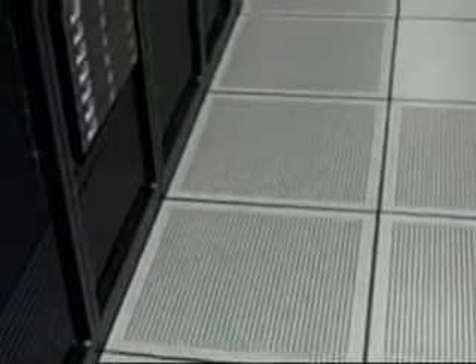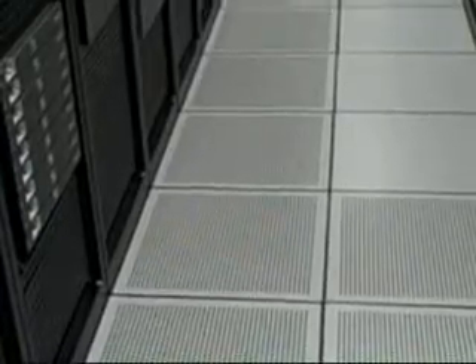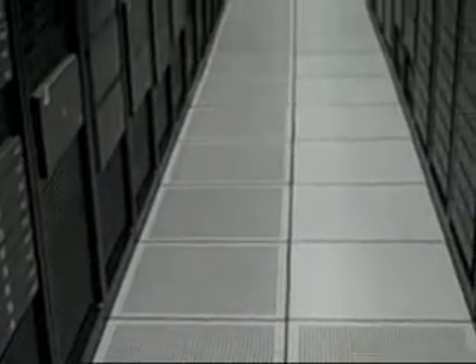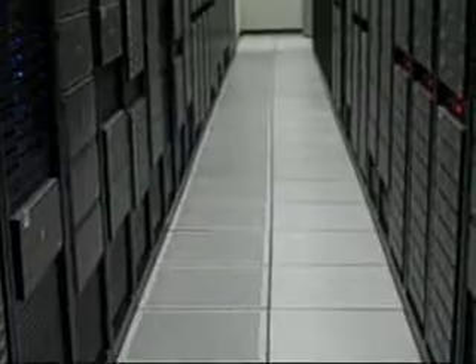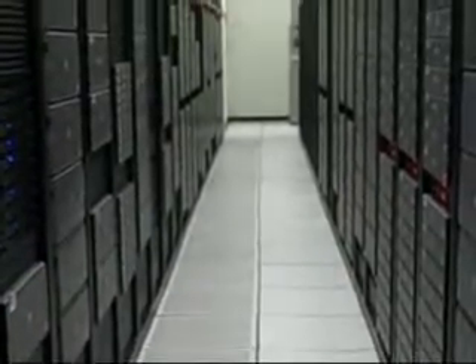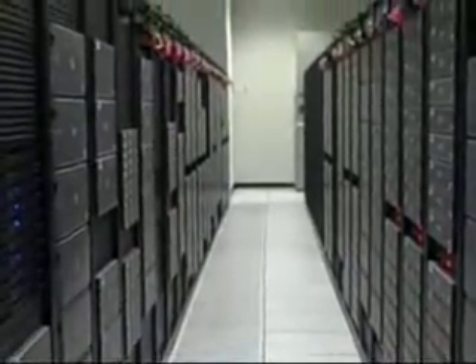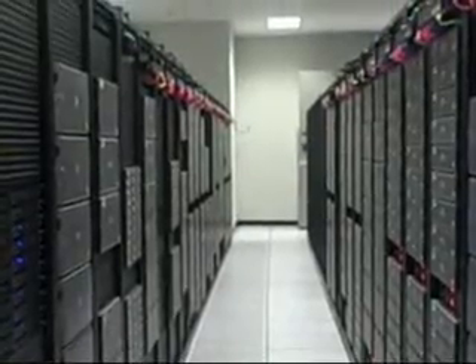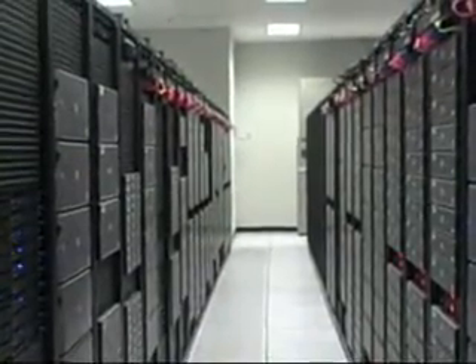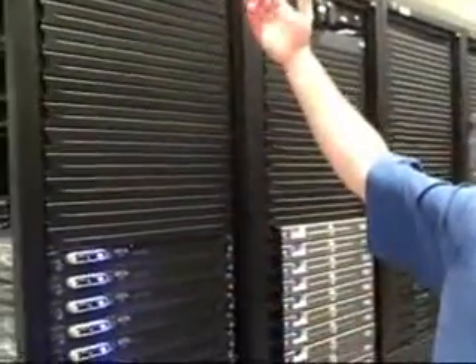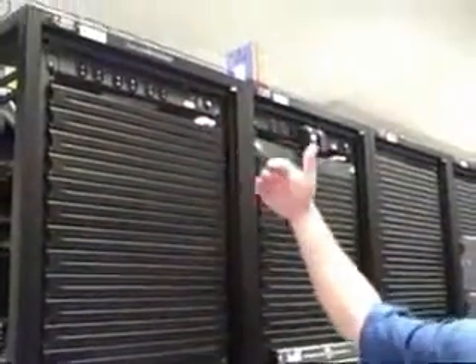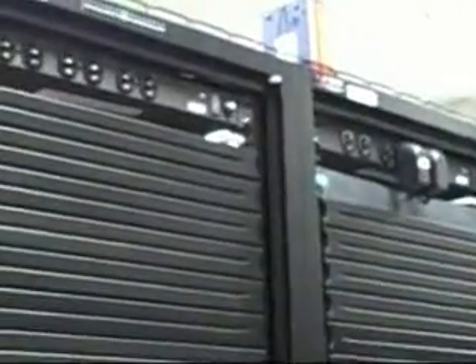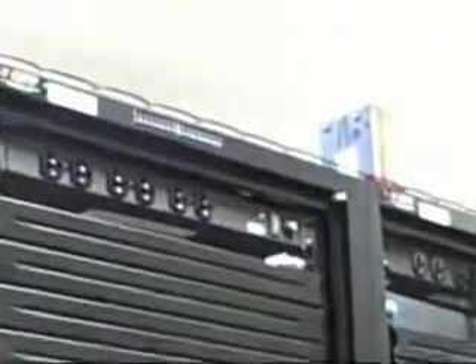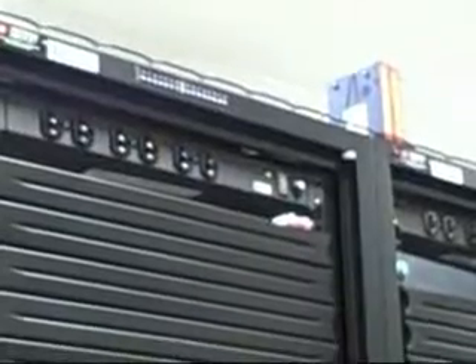The Planet first instituted fundamentals such as setting up their data center in a hot aisle, cold aisle configuration and installing perforated tiles in certain locations to get the cold air where it needed to go, to the front of the servers. Then Jeff Lowenberg took it to the next level. So we use the Uptime temperature strips to monitor the temperature at the top of the cabinets. Helps us regulate the temperature in the data center with our perforated tiles and with the set points on the air conditioner.